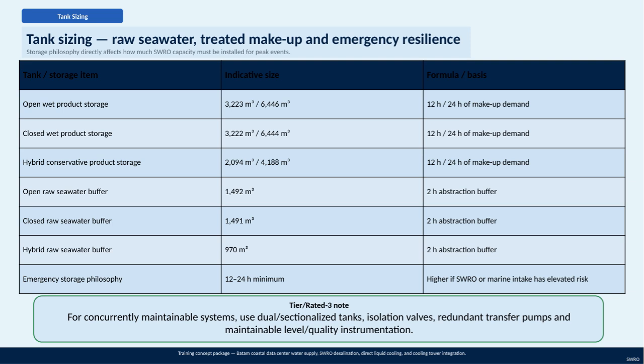For raw seawater buffers, we maintain around 1,500 cubic meters for open and closed systems with a 2-hour abstraction buffer. The hybrid raw seawater buffer is a bit smaller, just under 1,000 cubic meters. Our emergency storage philosophy is critical. We aim to have at least 12 to 24 hours of water stored to manage any sudden issues. This is particularly important if the SWRO system or marine water intake is at a higher risk of disruption. Lastly, for systems that need to be concurrently maintainable, like Tier or Rated 3 setups, we incorporate dual or sectionalized tanks, isolation valves, redundant transfer pumps, and maintainable instrumentation for level and quality. This ensures reliability and continuous operation even during maintenance activities.